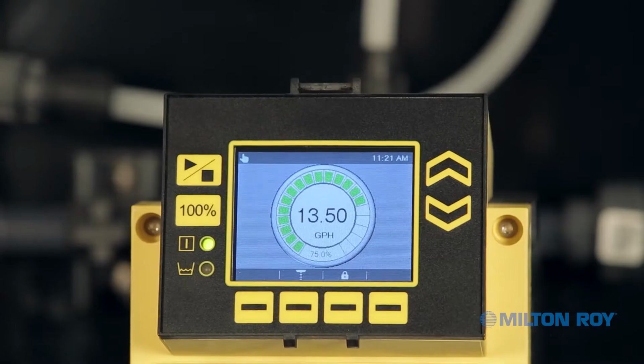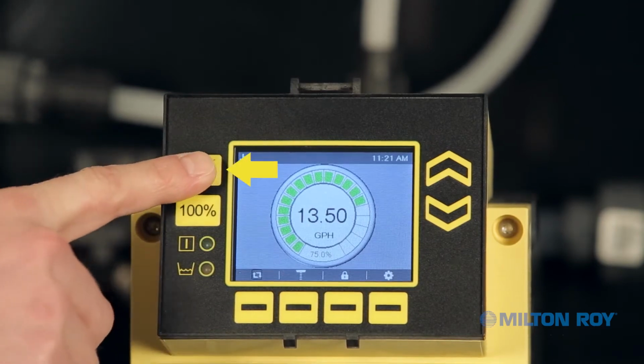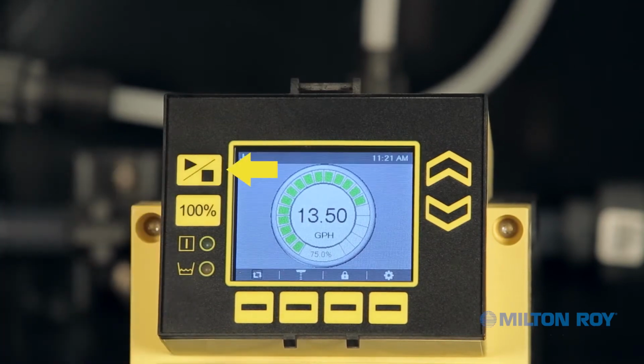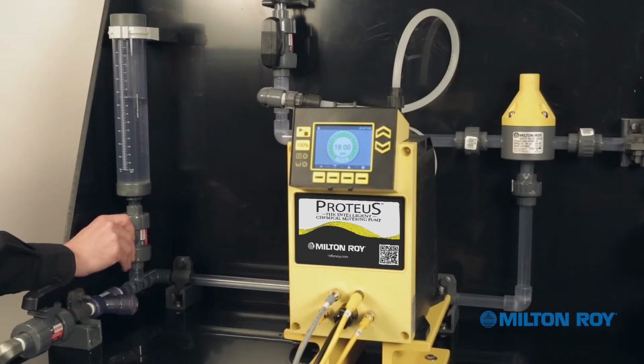To prepare for calibration, first, make sure the pump is stopped. If you need to stop the pump, press the Start/Stop button located on the left of the display screen. Notice the pump status indicator icon and its corresponding LED. If the green LED is illuminated, the pump is operating, and when the LED light is off, the pump is stopped. Once you stop the pump, fill your calibration column.